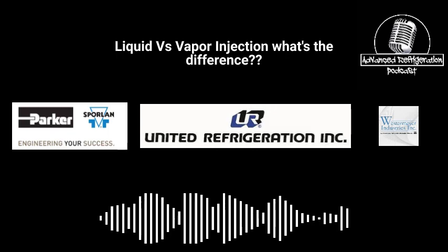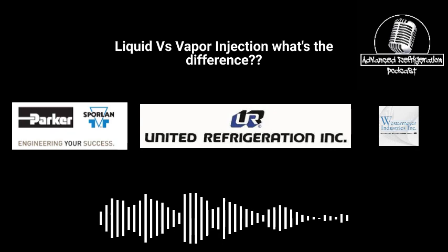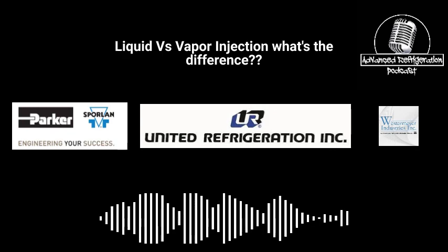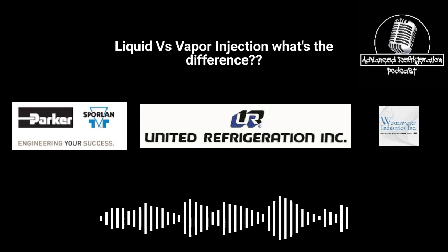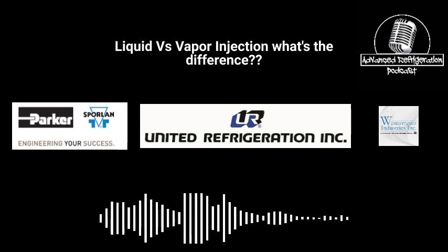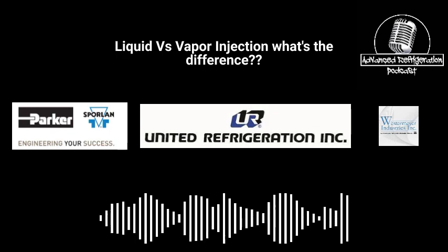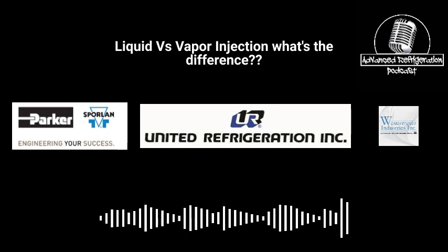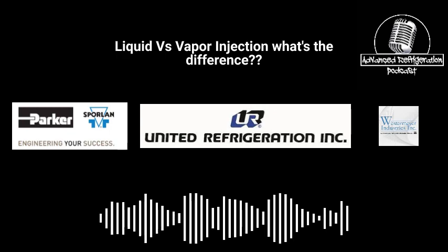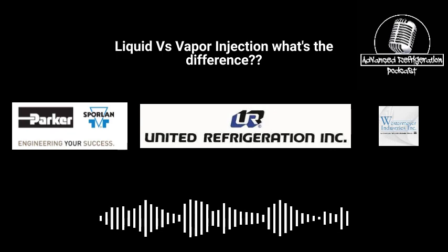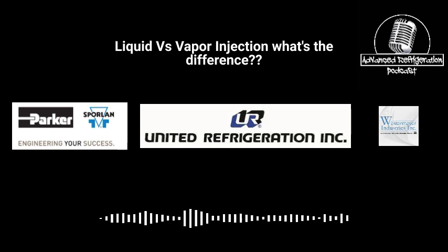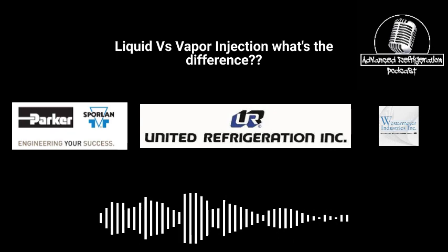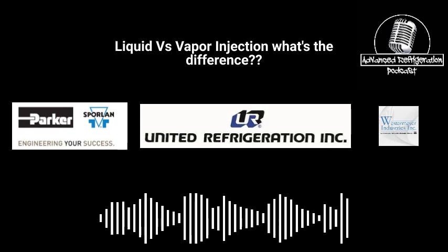Now, the reason you have liquid injection and vapor injection, there's a few reasons. When you use liquid injection, nothing is free. You're using BTUs, you're using capacity of the compressor. It requires work in order to cool that compressor off. That cooling effect comes in somewhere, so it adds to the kW of the compressor. So it makes that compressor less efficient by injecting liquid in there. You're taking up some of that capacity. So it's not free. That's why, back in the day, they only used liquid injection, because that's all they had. Now in comes vapor injection.